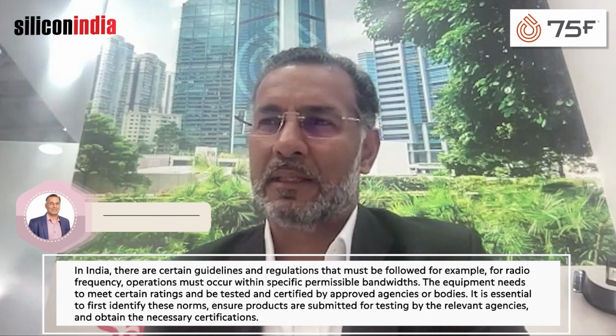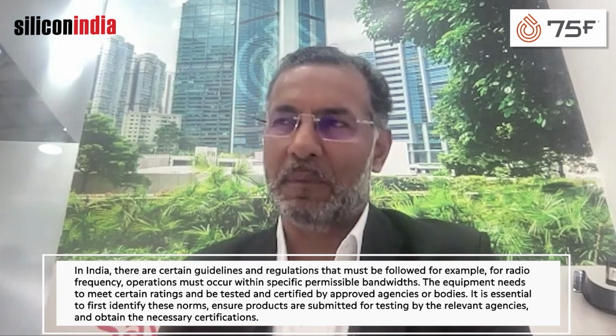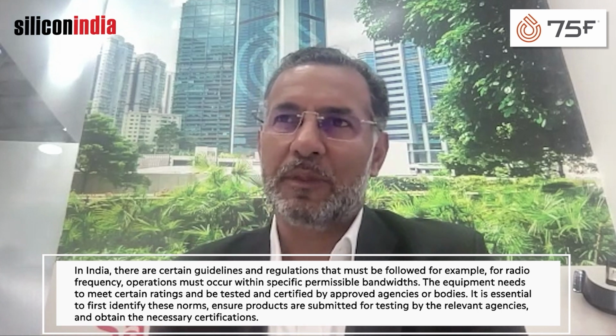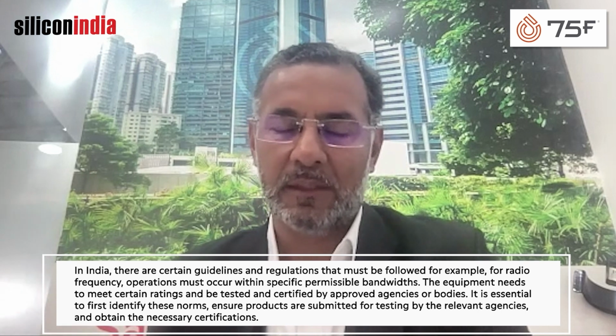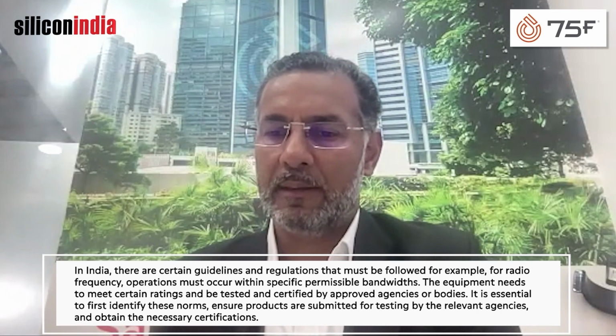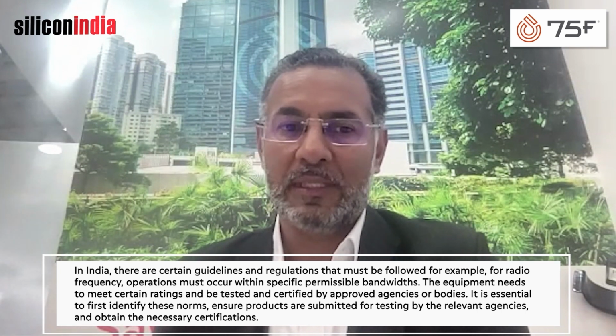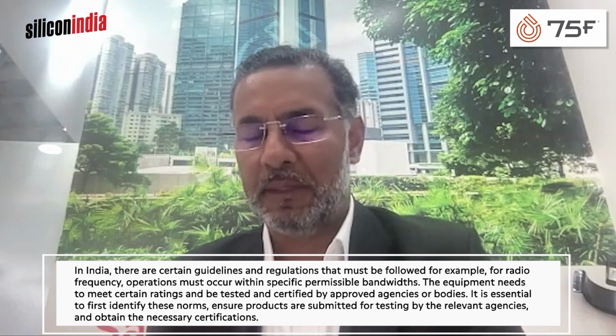On the regulatory framework - yes, there are some guidelines and regulations one needs to navigate. In India there are certain standards; for example, for radio frequency, one has to operate within certain permissible bandwidths. The equipment has to be of a certain rating, tested and certified by approved agencies or bodies. So those are norms one needs to identify, submit products for testing by the relevant agencies, and obtain certifications. In case they don't pass, that feedback needs to go back to product design and engineering, necessary changes are made, and the product is submitted again for certifications and approvals.